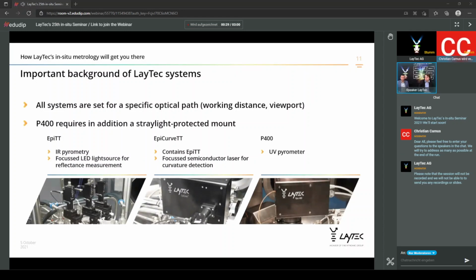What you should always keep in mind is the important background of the LayTec systems. All of our systems are set for a specific optical path. That means especially the working distance and the viewport on your growth system, because this is strongly influencing the optical measurements. In addition to working distance and viewport, the P400, because of using this UV range for the pyrometry, needs in addition a stray light protected mount.